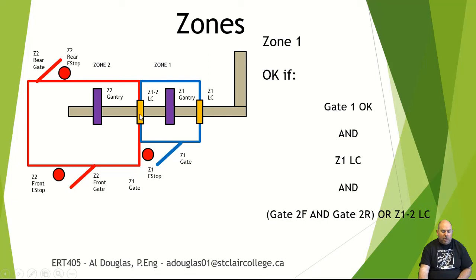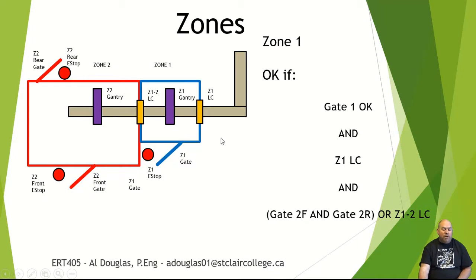The other side of the cell is made up by the zone one-two light curtain. Zone one's perimeter is still okay if that light curtain is breached, as long as the entire zone two perimeter is intact. So if this light curtain is broken but the rear gate and front gate of zone two are both okay, we effectively have one big fenced-in area and it doesn't matter what's going on between the two zones. This is how boxes can travel between zone one and zone two without interrupting safety flow.